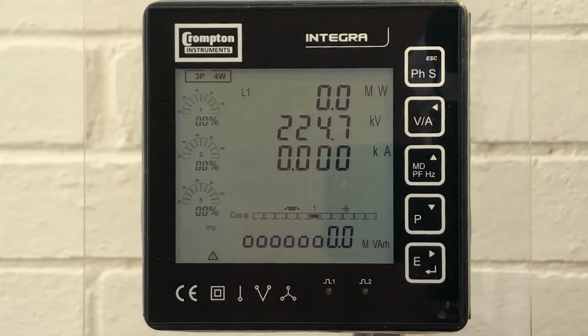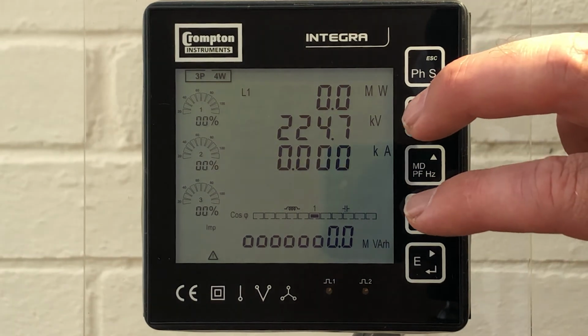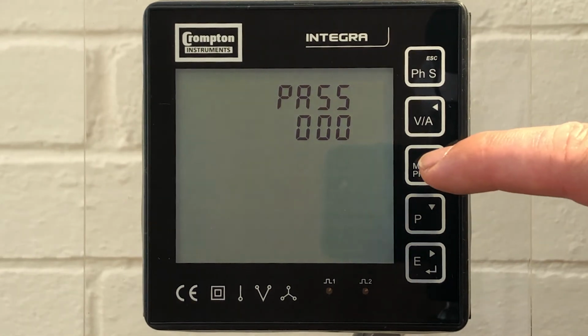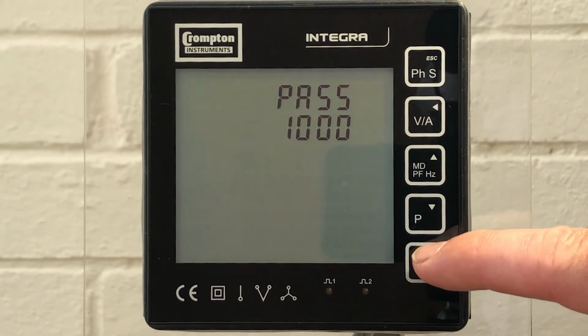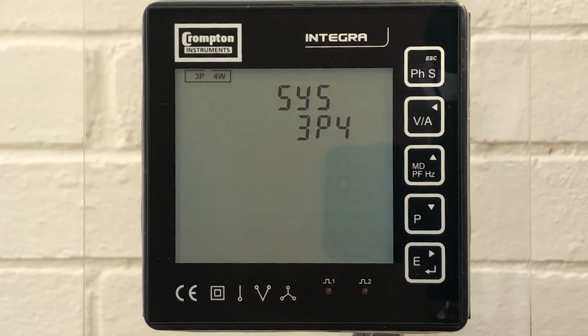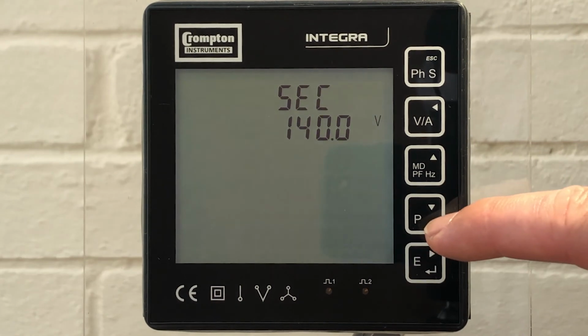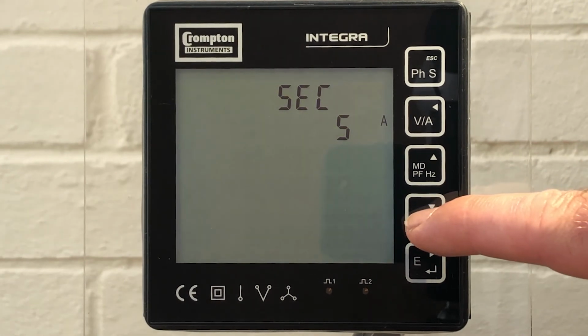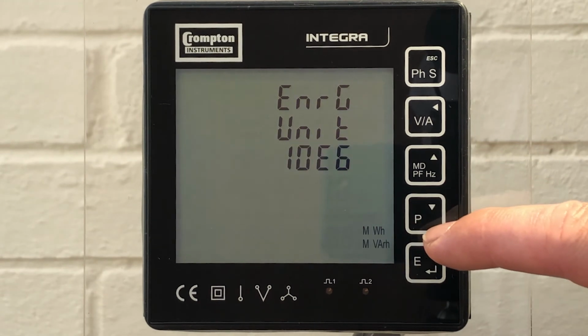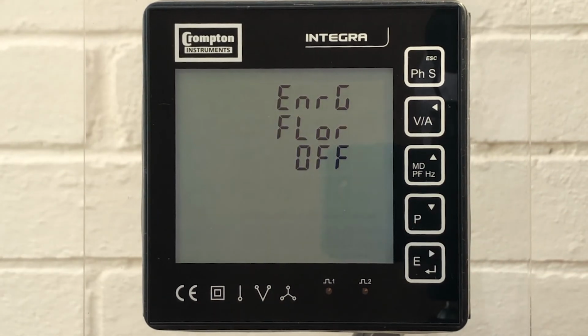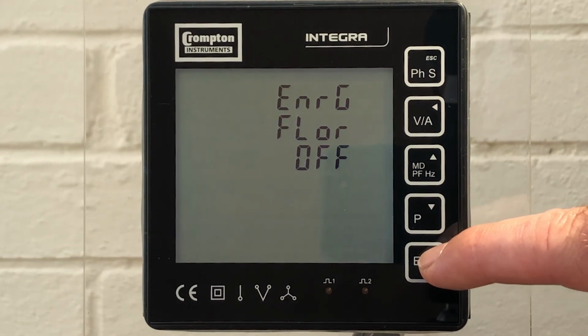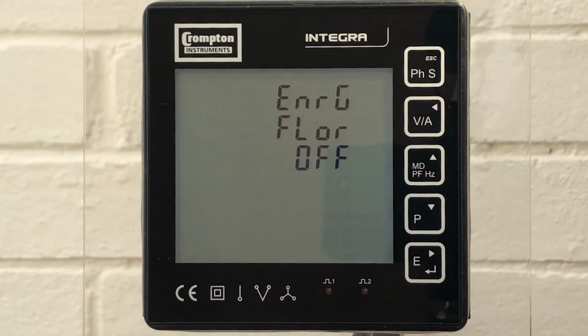You may notice there is an exclamation mark in a triangle at the bottom left hand side, and that would indicate that we have our low power threshold turned off. If you want to remove this, you'll need to go back into the setup menu and navigate to the energy floor setting, and hold E to enter. You can see it's off at the moment. We're going to hold E and turn the energy floor on, and this will prevent any creep caused by electrical noise.